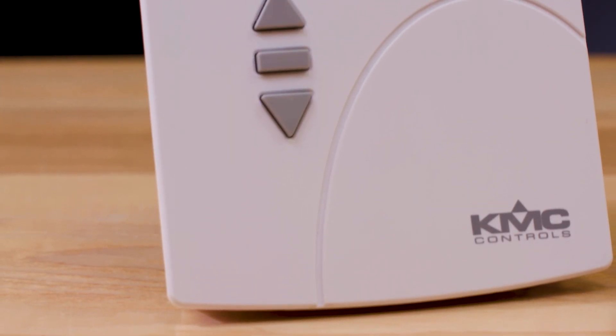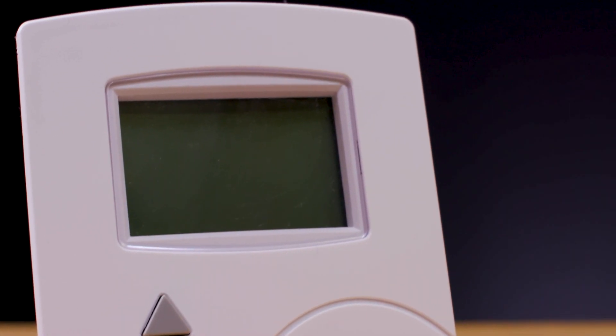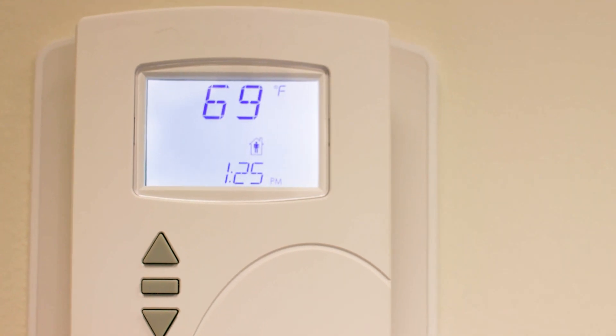The STE 9021, like all models in our STE 9000 series, features a user-friendly three-button interface for simple system viewing and adjusting. The upper LCD display shows room temperature and set points, while the lower display shows local time and can be enhanced to also show relative humidity in rotation. Both displays can be configured to show any controller default or calculated analog or binary values, such as airflow or energy consumption, and you can show multiple values in rotation.